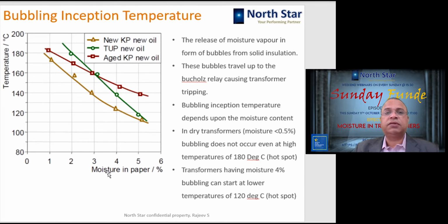How? Here is a concept called bubbling in the transformer. The transformer is subjected to the release of moisture, basically moisture vapor from the solid insulation in the form of bubbles. Okay, here in this graph we are showing three different kinds of cases. One is new kraft paper with new oil, second is thermally upgraded paper with new oil, and third is aged kraft paper with new oil. So in all the cases, the oil is new but the insulation is of a different type. So just have a look at the new KP and new oil situation for understanding. You can see here, this is the BIT, that is bubbling inception temperature.